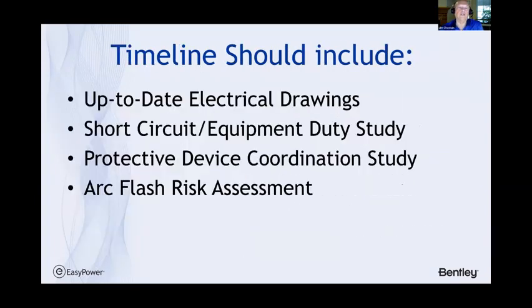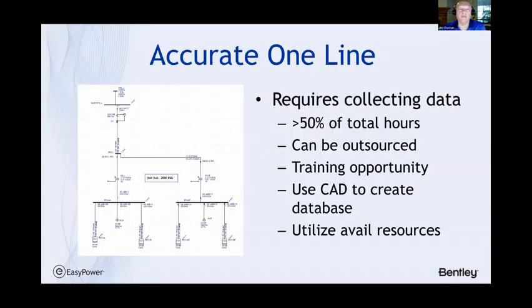Now, the timeline should include up-to-date electrical drawings, short circuit equipment duty studies, protective device coordination studies, and then an arc flash risk assessment. It's virtually impossible, in my opinion, to have any semblance of an electrical safety program if you don't have an accurate one-line diagram. And unfortunately, the data collection on an existing plant can be very time consuming.